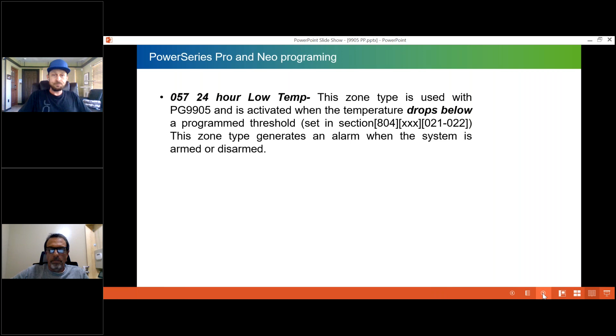So how do we set the threshold, right? Again, we have 3 different zone types for this, or what you may be used to is called a group type. 52 is the non-alarm, 56 is your high, 57 is your low. And then after you enroll the device, which enrolls just like any other PowerG, so you get the auto enroll function, all that good stuff, depending on the definition, you're going to set your threshold for your temperature warning and your temperature alarm. So if it's high or low, you have a warning and an alarm that can be programmed in to best fit that scenario, right?